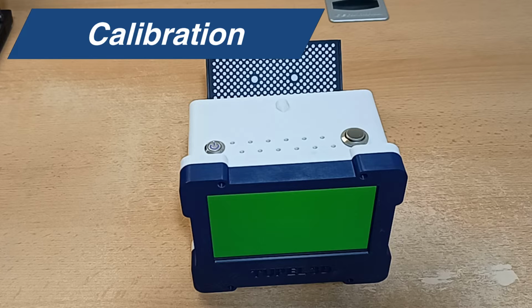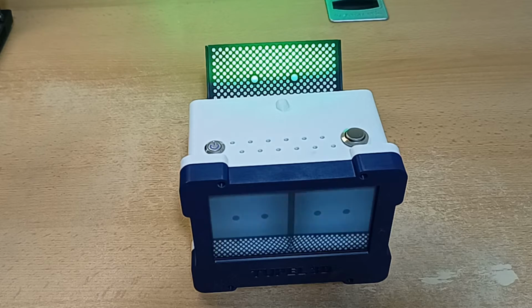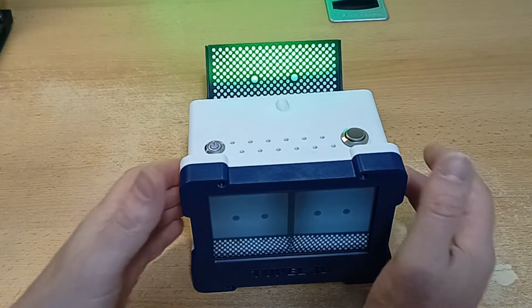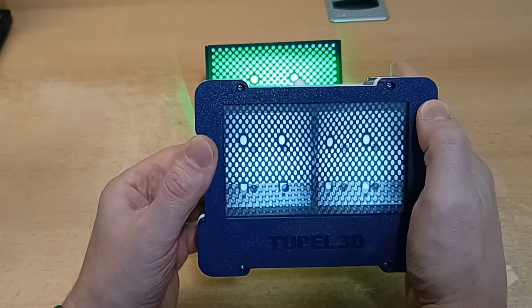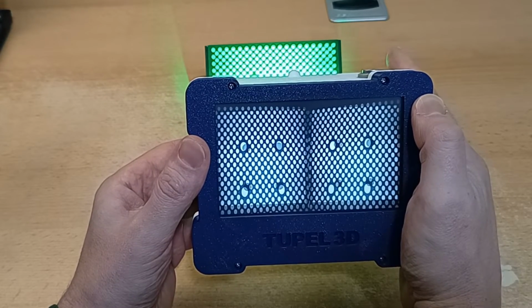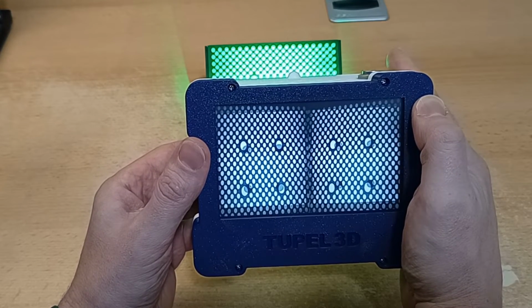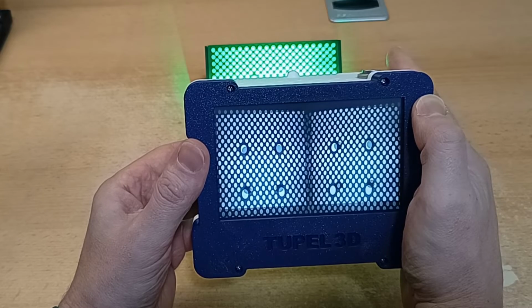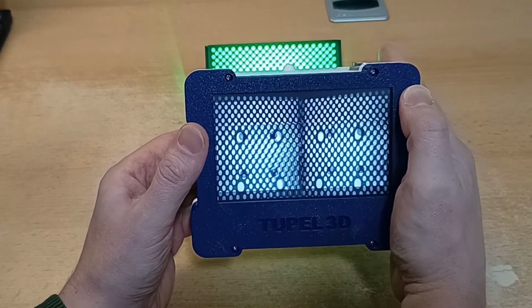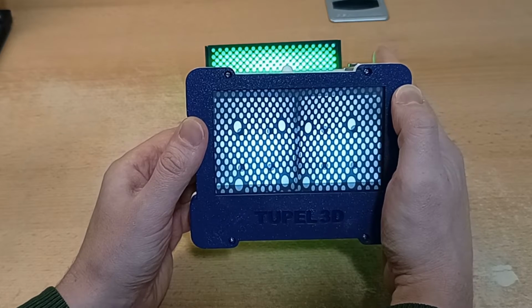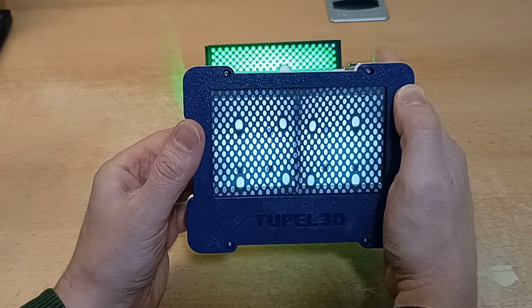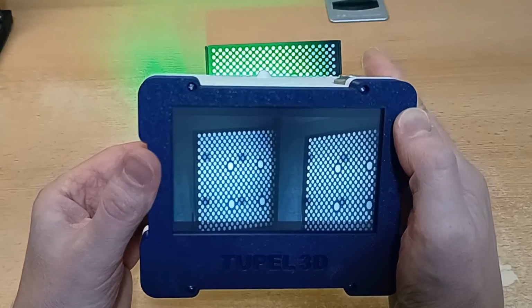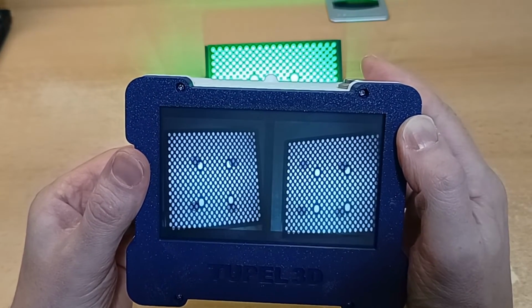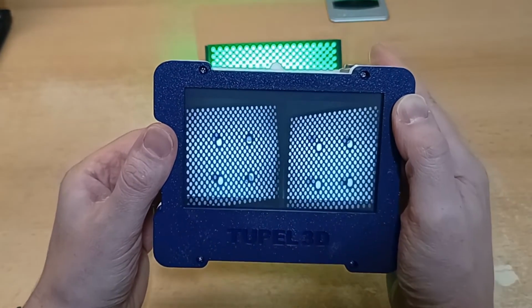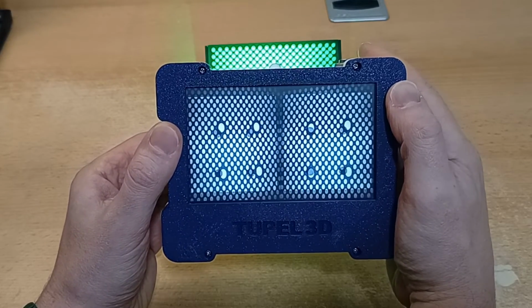Let's take another look at calibration. When you're asked to calibrate the unit, the scanner starts up showing 4 faint dots, and you should align these with the 4 big dots on the calibration plate. There are actually 2 cameras, and so 2 images. Note that if you are too close, you have no chance to line up the big dots for both cameras. It's the same if you are too far back. But when you are at the right distance, everything lines up pretty well. So then you press and hold the shutter button to start capturing.